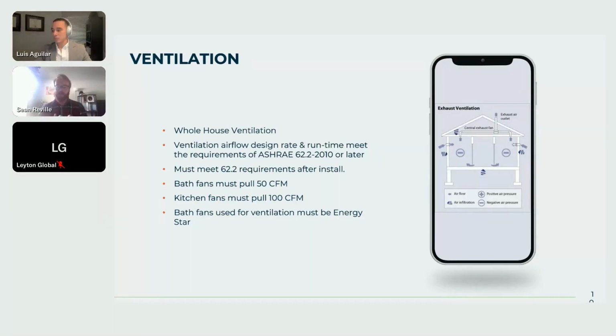All right, ventilation. So you have to meet ASHRAE 62.2-2010 or later for each dwelling unit on a project. The 62.2 requirements must be met after install, so it's very important to take into account line loss and static pressure when you're designing your system to meet the 62.2 requirements. Bath fans must also pull at least 50 CFM, and kitchen fans must pull at least 100 CFM. There are a couple of niche alternatives for that if you're using continuous running fans or something like that, but that's generally the requirement, and that is all what it has to be at final test out.